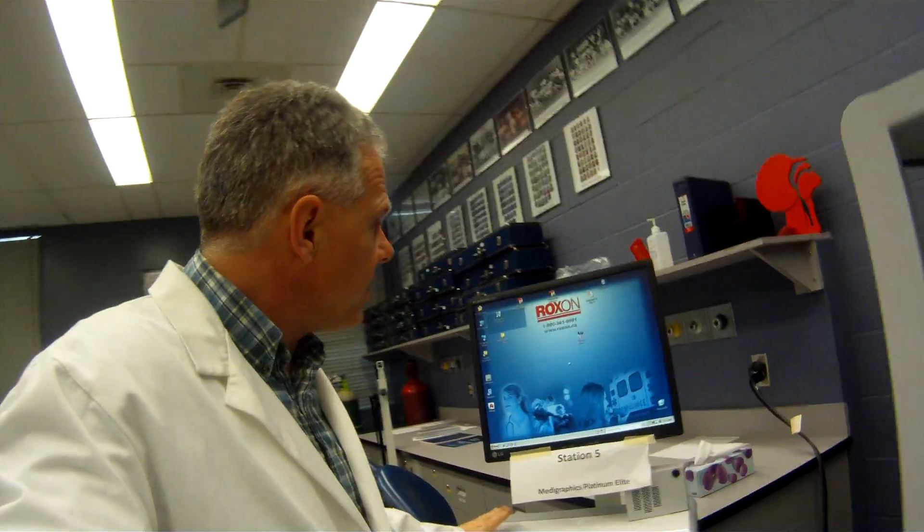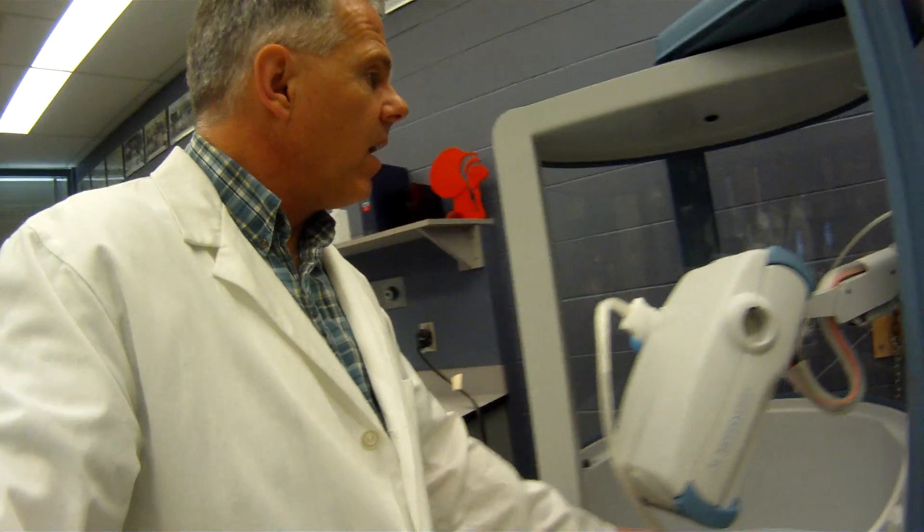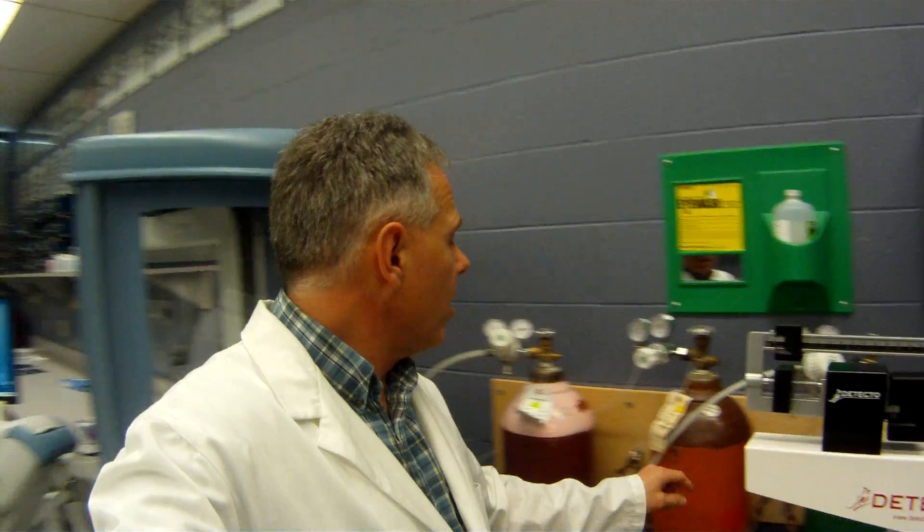The basic setup is we have a computer here, and all the required equipment is built right into the base of the unit. We've got our gas tanks here — we've got oxygen, helium, and our DLCO mixture. So we can do all the basic tests, such as nitrogen washout, DLCO, basic spirometry, plethysmography, carbon monoxide uptake, and single breath nitrogen washout. We've got a wide variety of equipment here.